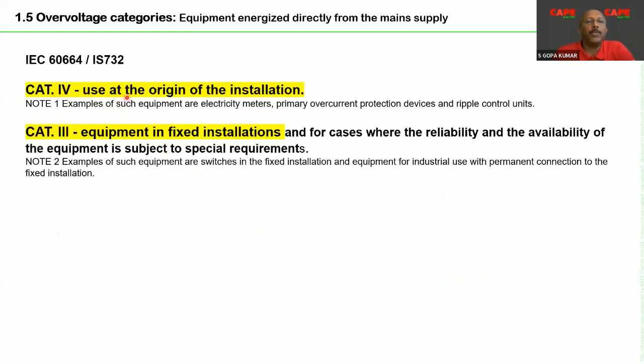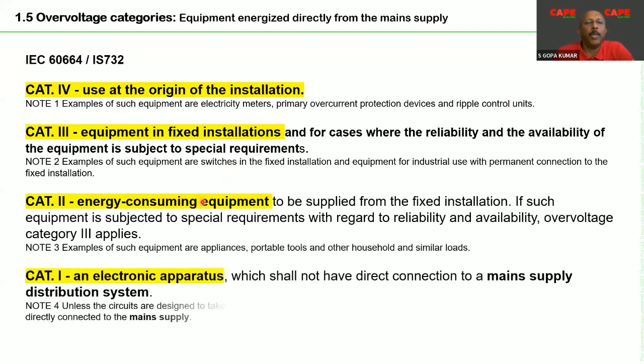Category 4 is a device which has to be used at the origin of the installation. That means wherever your electrical installation starts, at the mains incoming panel, all the electrical apparatus which you are using, such as the switchgears, the meters, the CTs, the MCBs or whatever, all these devices must be of installation category 4. Of course, an MCB probably in a large panel is not possible. Category 3 is equipment in fixed installation. I have some examples I will show you. Category 2 is energy consuming equipment, and category 1 is an electronic apparatus. So these 4 categories are mentioned in the standard.